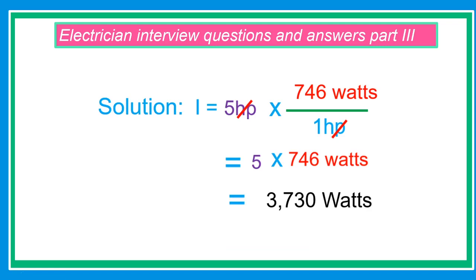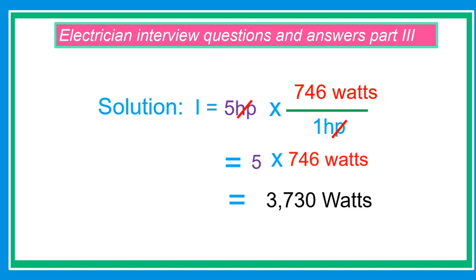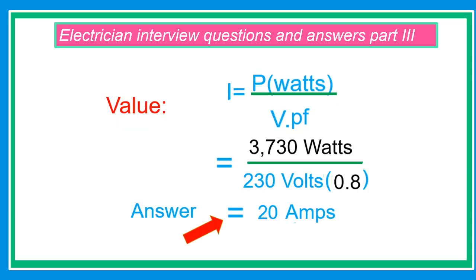Solution to the problem above. In this problem, the given is 5 horsepower, 230 volts, and 80% power factor. Solution: First, we're going to convert the 5 horsepower to watts. 5 times 746 watts equals 3,730 watts. We already converted the horsepower to watts. The answer is 3,730 watts. Now we're going to substitute: 3,730 watts divided by 230 volts times 0.8 power factor. The current is 20 amperes.